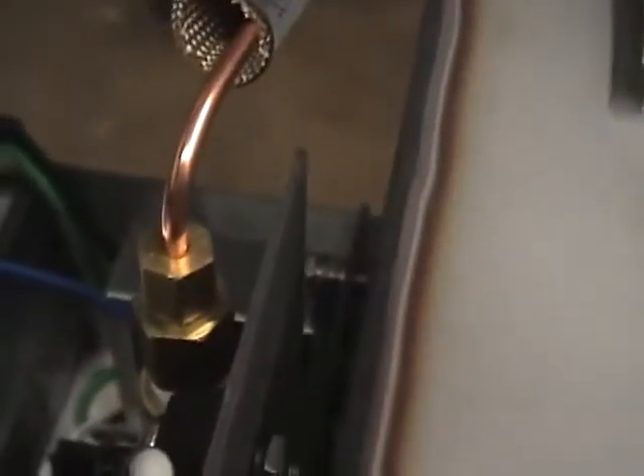Replace the 1/8 inch copper line back into the pressure transducer, and then finally just tighten back again the 2 bolts on the bottom that hold the electrical plate. And one final thing, remember to plug the power back in to the pump with the 2 blue wires.